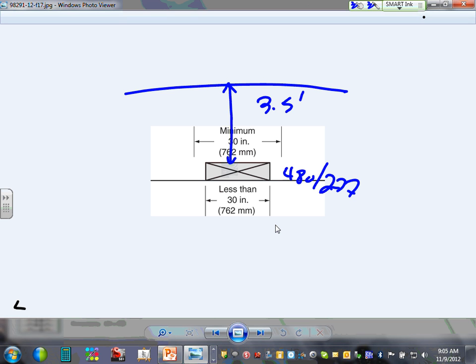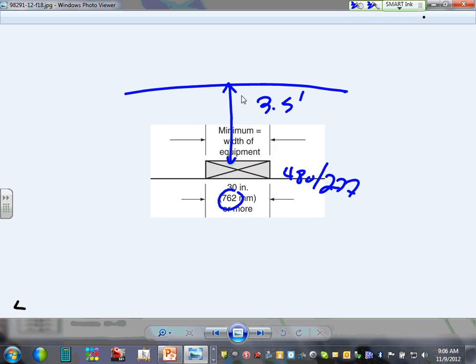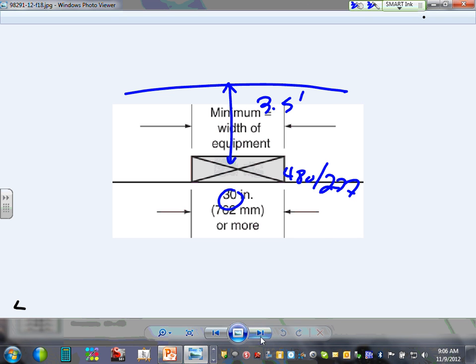Now I want you guys to look at the width. The width is a minimum of 30 inches or the width of the equipment. Can I have thumbs up, Chad? So if this is a panel, the width will be the width of that, right? Or 30 inches, whichever is more. So that's the width. Remember that width? It has to be 30 inches or the width of the equipment. The depth, typically 3.5, 4, depending on the voltage and the condition. The width is 30 inches or the width of the equipment. That's your clearance.